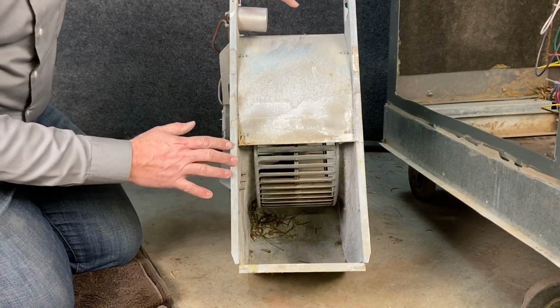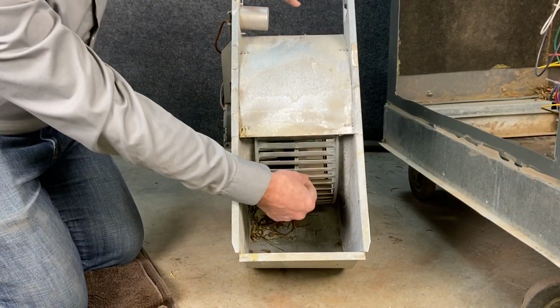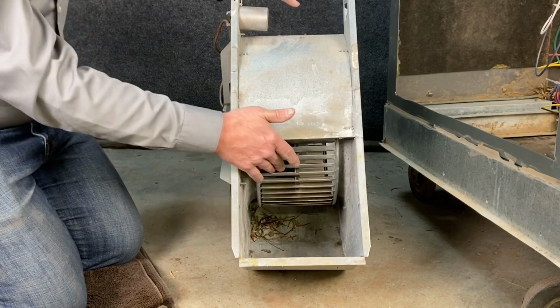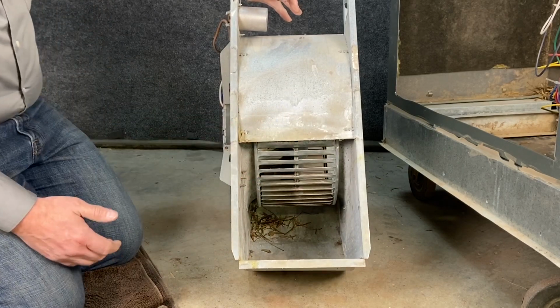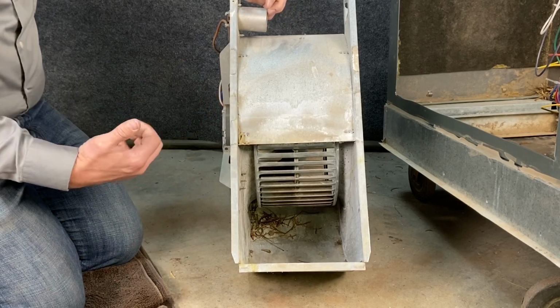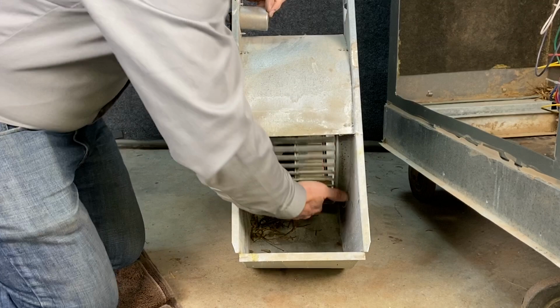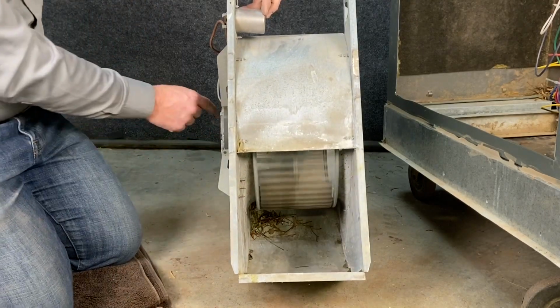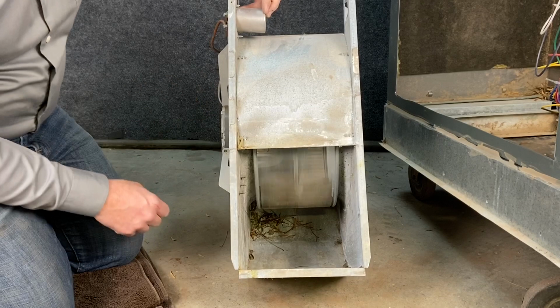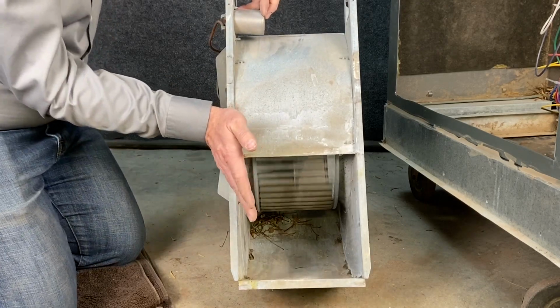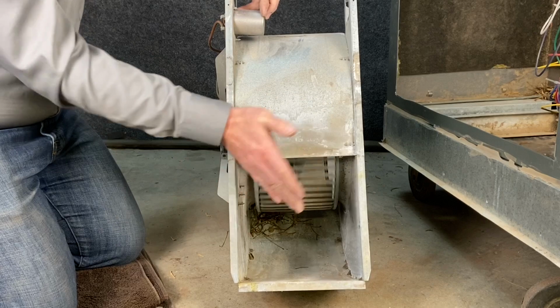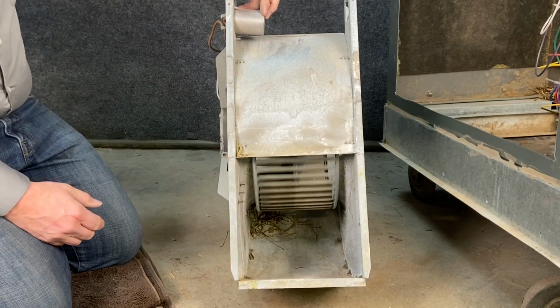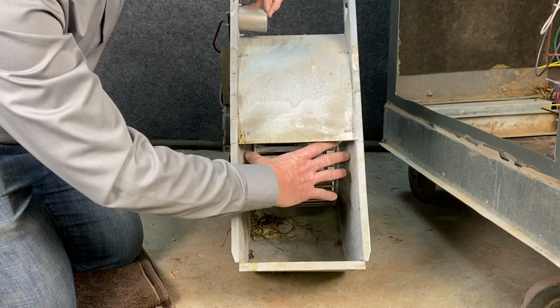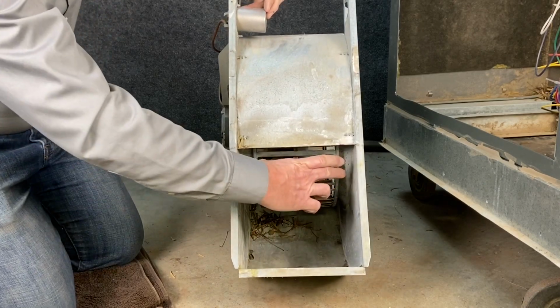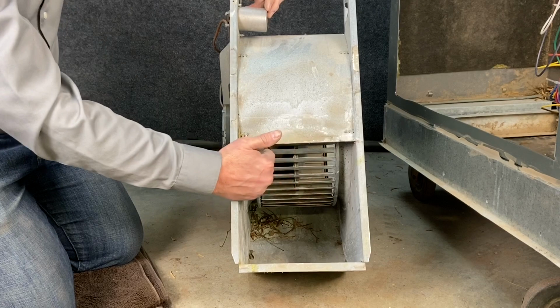So here we have our blower taken out. And on these fins, there's a lot of dirt built up on this. So we need to take this apart, wash it, and clean it before we put it back together. This is part of the maintenance that we do, is we take this apart and clean it. When we put it back together, you always want to spin these to see how well it's turning. This one has a stick in there making some noise. But if you notice that the blower wheel is turning pretty straight, sometimes you'll see them wobble like this, and that's where you know you have a bad blower wheel that you're going to have to replace. But also notice how the blower wheel should be centered between this housing right here. Sometimes I see technicians install them too close to one side or the other and allows air to bypass.